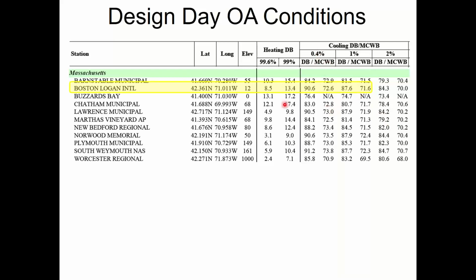So in Boston, I should design for 8 degrees in the winter and 90 or 91 degrees in the summer. Will it ever be 96 in Boston? Yeah, sure, it'll be 96. But that's not what I'm designing for. That'll happen, but it's a freak occurrence, and it's brief. It's not going to be all night long, right? And if it is, for the one time it happens every 80 years, fine. I'd rather be awesome for the entire year and have one day where it's not awesome, if I had to choose.